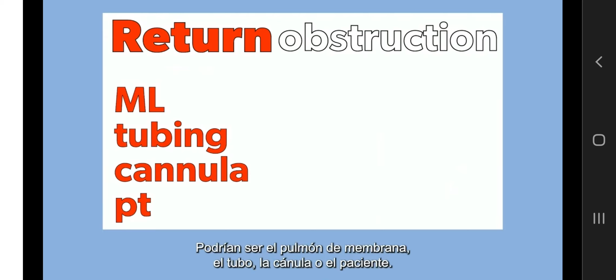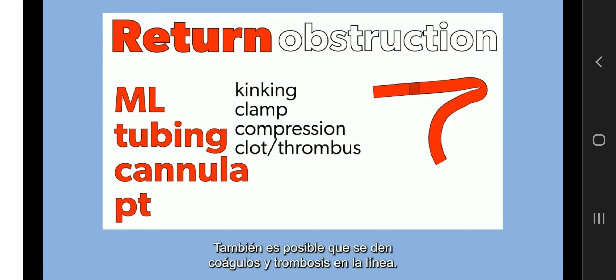For return tubing, a kinking of the line or a clamp left on return tubing at ECMO initiation may be a compression of the line, such as the line under the leg of the patient during or after mobilization, or the line under the wheel of the ECMO cart. Line clotting and thrombosis may also potentially occur.